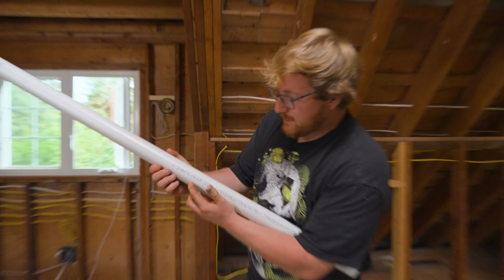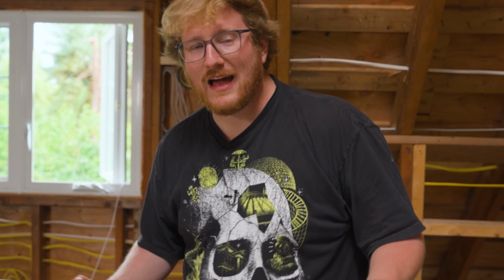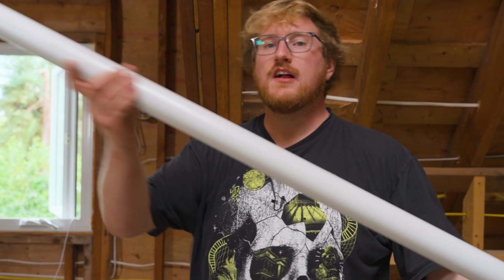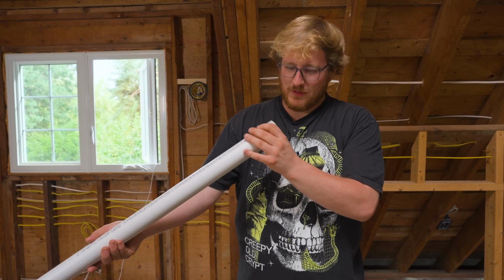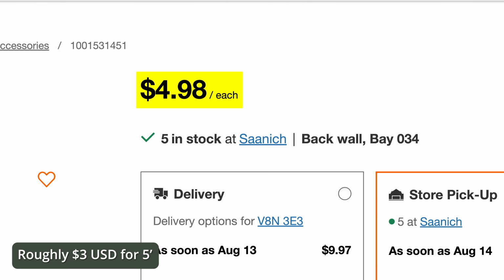And what makes it even more devious is that this isn't expensive electrical conduit. In fact, this is PVC vacuum tubing. You wouldn't be allowed to run high voltage in this, but since it's technically not acting as protection for our low voltage wiring, it's just like an organizer effectively. It can be whatever tube we want, which is great because this stuff is really cheap.